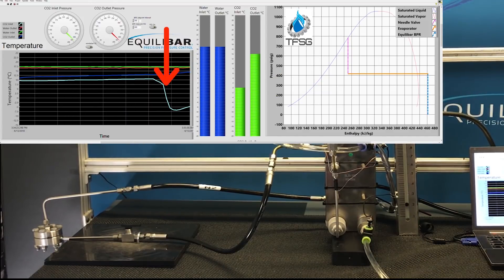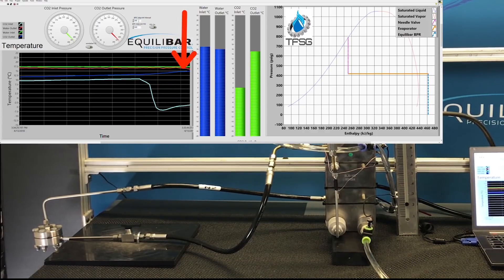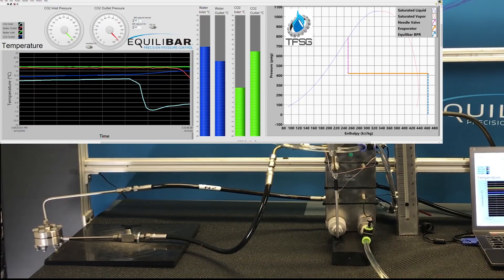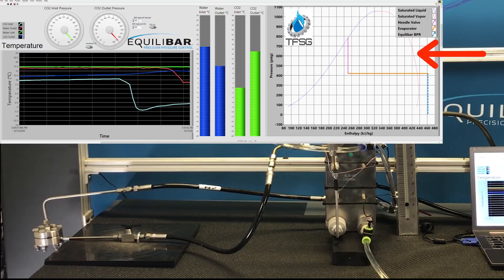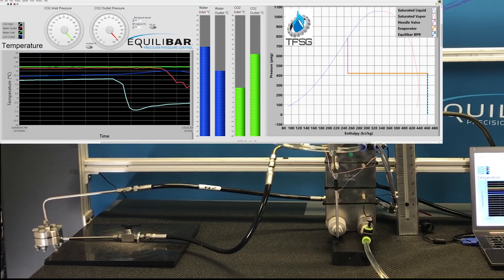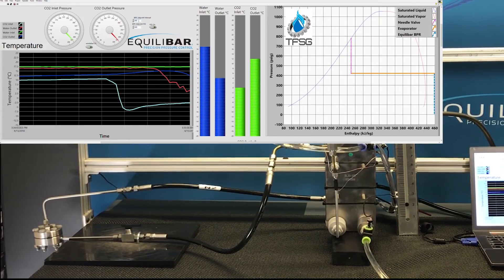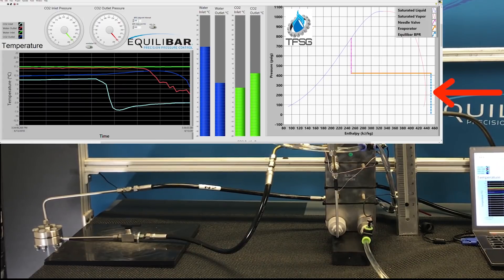The light blue line on the temperature plot represents the CO2 inlet temperature whereas the red line represents the heat load outlet temperature. The graphic on the right is a representation of the pressure versus enthalpy curve for CO2. The light red line represents the saturated vapor line and the solid orange line indicates evaporator pressure which is controlled by the Equilibar. The vertical blue dashed line represents the pressure drop across the Equilibar.